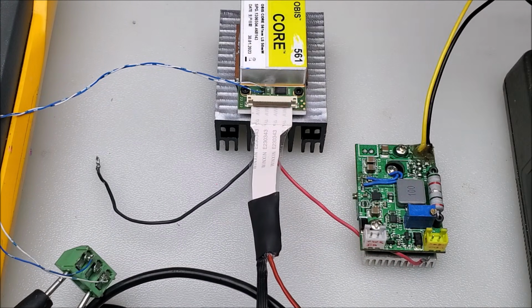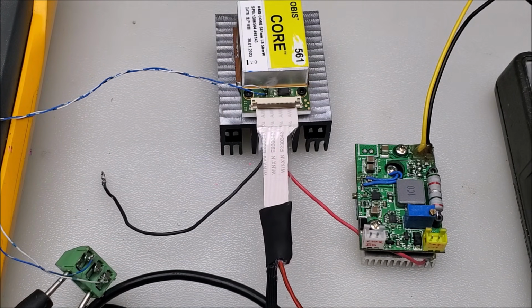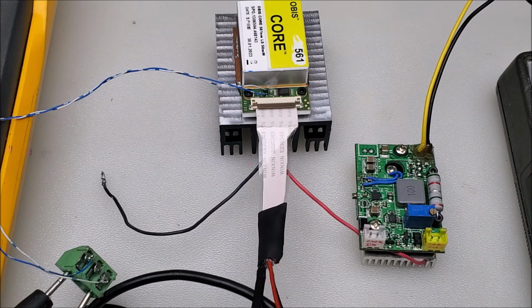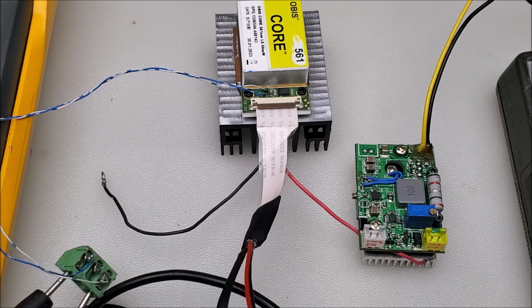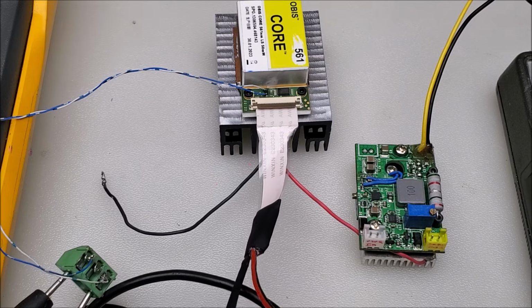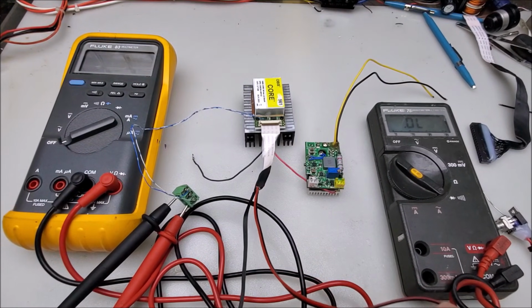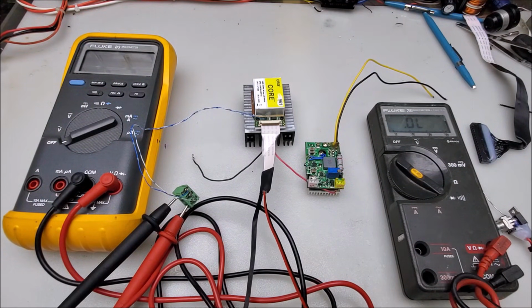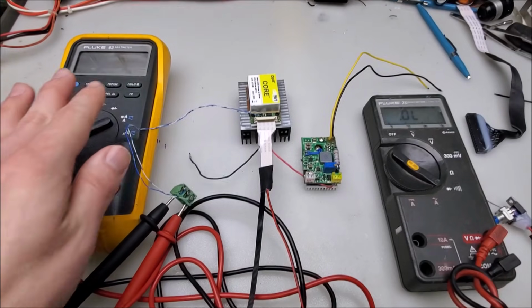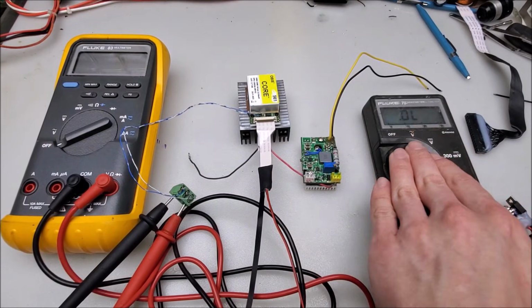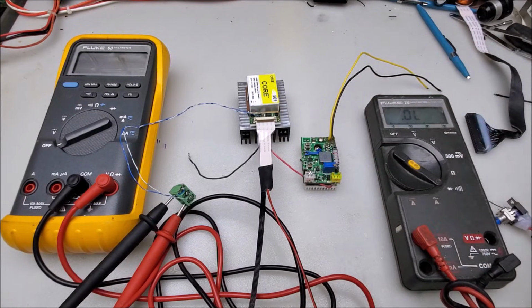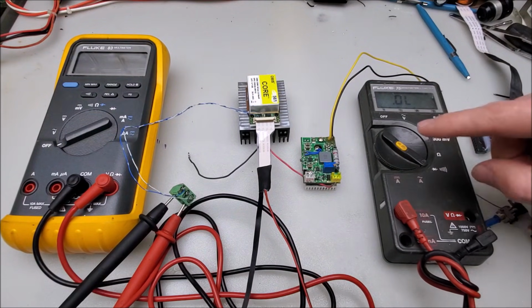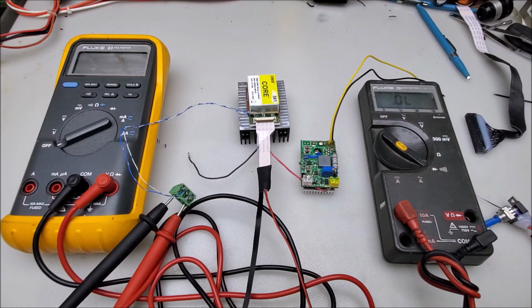Just like that. Let's make sure that it's actually connected properly. I'm going to throw this in diode check mode, and I should be getting about 1.4 across that one way, the laser diode way. And I do. Let's go ahead and zoom that out. And across the other way, I should be getting that Schottky diode voltage drop. Sure do. Okay, awesome. So we've got a way to read the voltage here, and I'm going to throw this meter in amps, reading the current, and place this in series with the laser diode and the output of the laser driver.